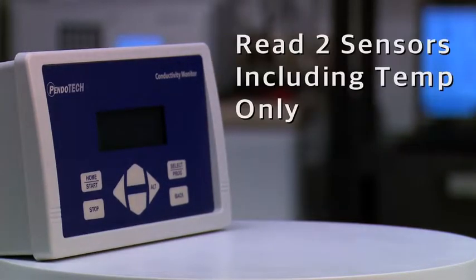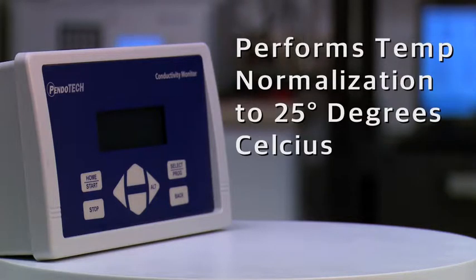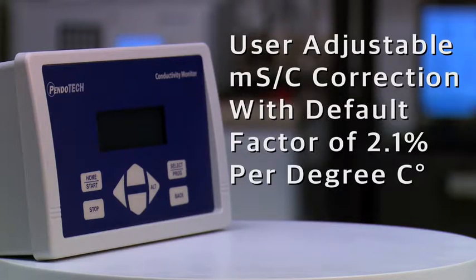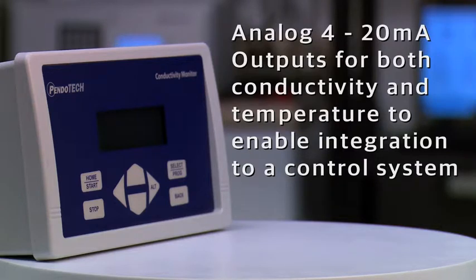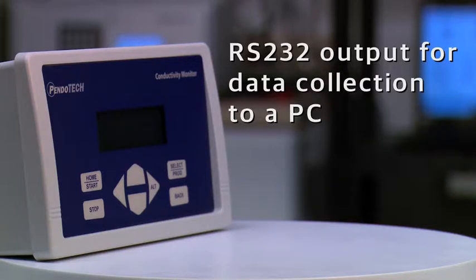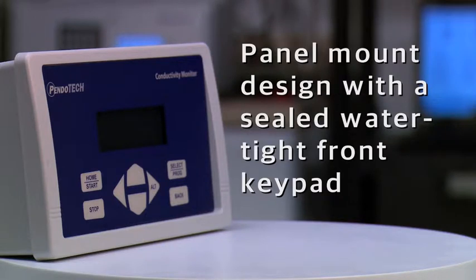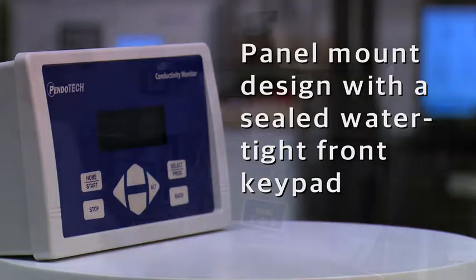It has the ability to read 2 sensors, including the ability to read temperature only, performs temperature normalization to 25 degrees Celsius, user-adjustable percent per degree Celsius correction with a default factor of 2.1% per degree Celsius, analog 4 to 20 milliamp outputs for both conductivity and temperature to enable integration to a control system, RS-232 output for data collection to a PC, and has a panel mount design with a sealed watertight front keypad.